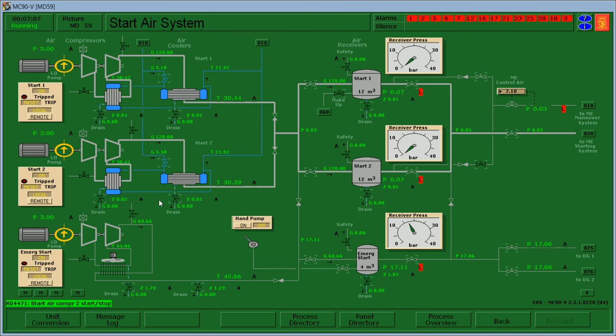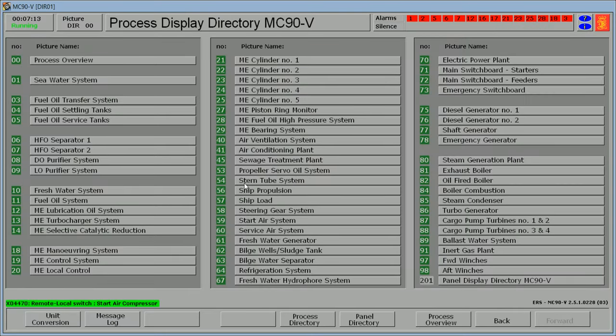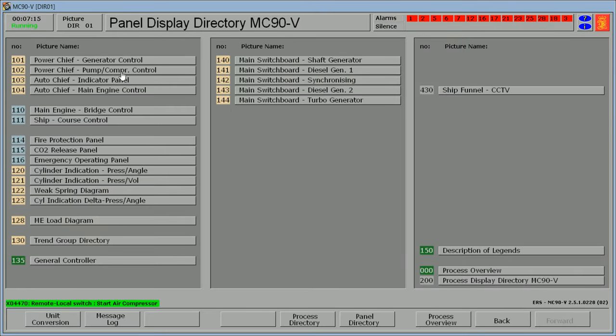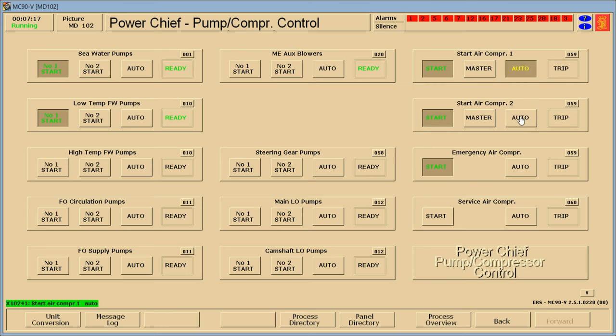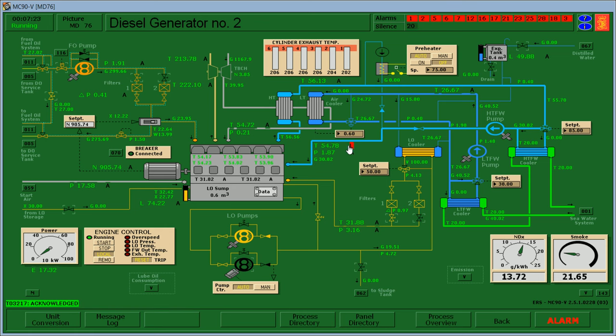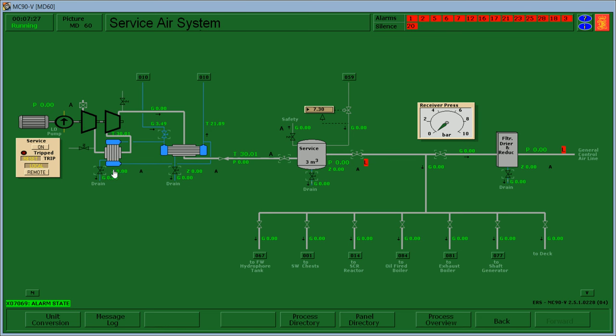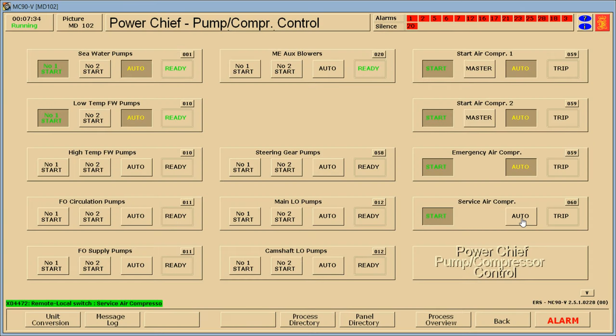Start the air compressors. Set to remote. Proceed to panel directory, power chief pump controls, air compressor 1, seawater. Then acknowledge the alarm. And proceed to service air compressor, press on, set to remote, and auto.